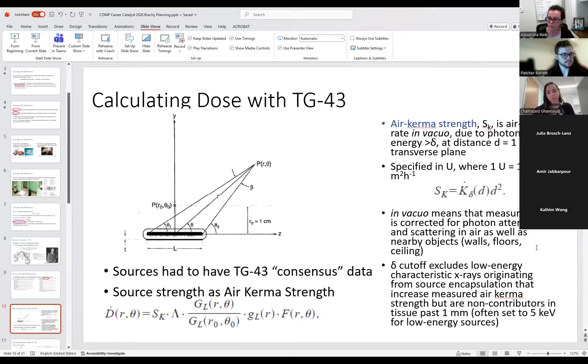So the dose rate constant was the second value here. And basically it is specific on the radionuclide and the internal design of your source. And what it does is it gives you the ratio of the dose in water at the reference point. And the reference point is at 90 degrees, so right here, and 1 centimeter away from the source.